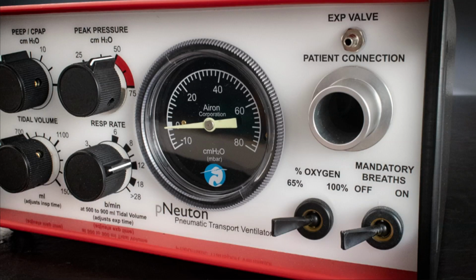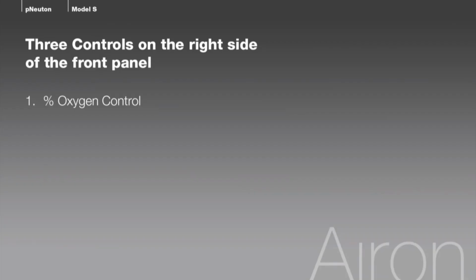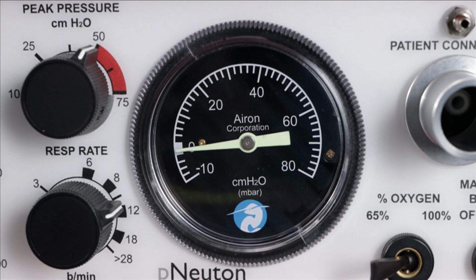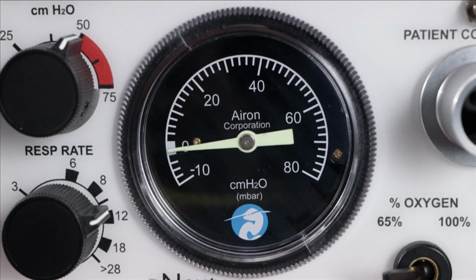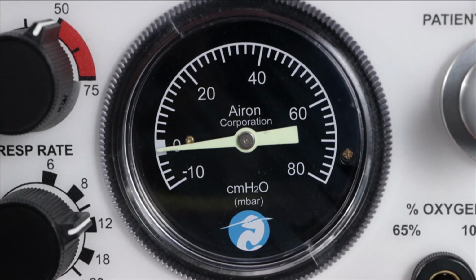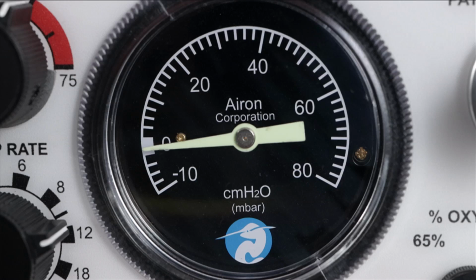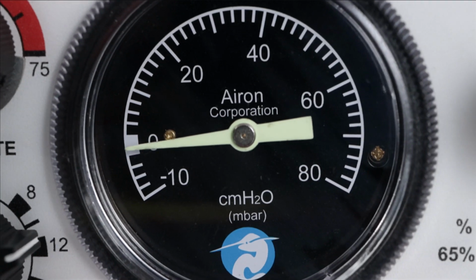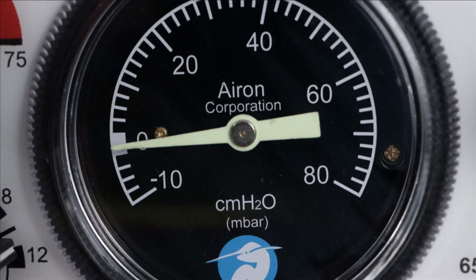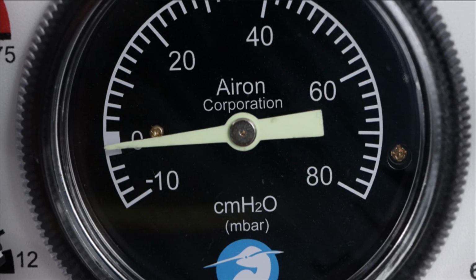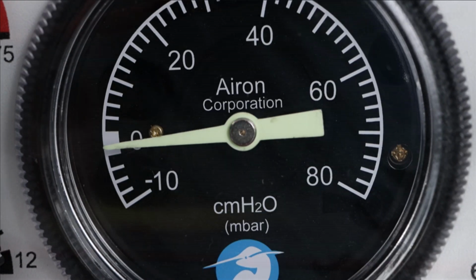Let's now move to the right-hand side of the front panel to discuss percent oxygen control, mandatory breaths, patient connection. First, you will notice that central to the front panel is the manometer pressure gauge, which gives a visual indicator of patient pressure for the CPAP PEEP and the delivered airway pressure for each breath. The manometer shows pressure in the patient circuit as it leaves the ventilator.